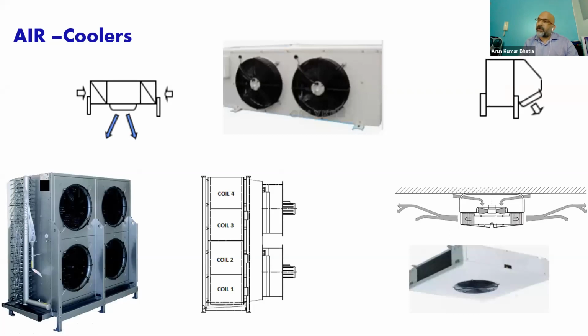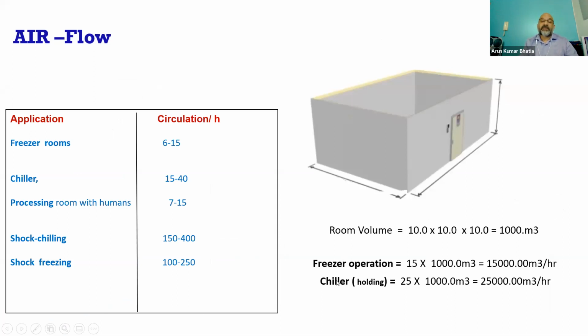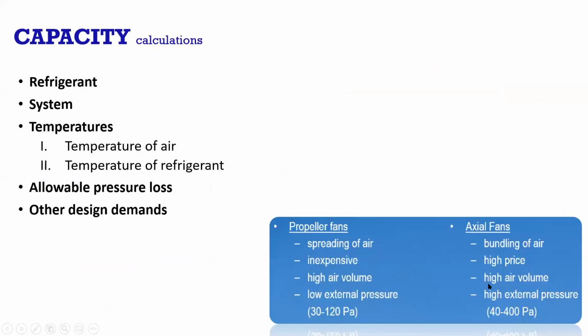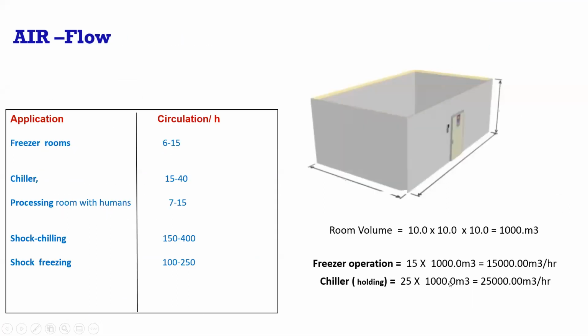I hope that's clear, but I can answer in questions. There are two types of chillers: one is a holding room, another is chilling. This example was for freezer application. For a chiller holding a product, the air circulation is 25 circulations, so 25 into 1000 means the same evaporator in the room should generate 25,000 meter cube per hour.